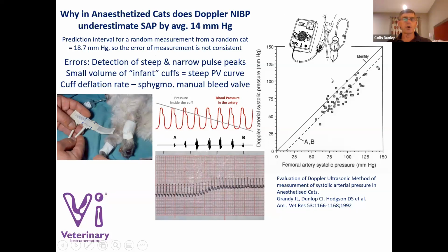And so this is work we did years ago looking at the error of measurement of Doppler versus direct pressure. If this was accurate, all these dots would be on the solid line. And if that was the case, this thing would be quite accurate. So in anesthetized cats, the error of reading of a Doppler is about 14 millimeters of mercury. And in fact, it's possible that Dopplers in cats are getting closer to the mean pressure because of this narrow waveform with a high spike on the systolic waveform.